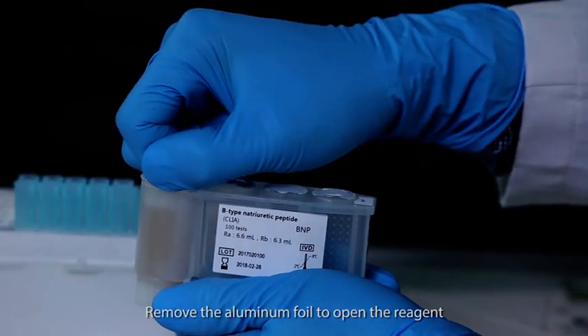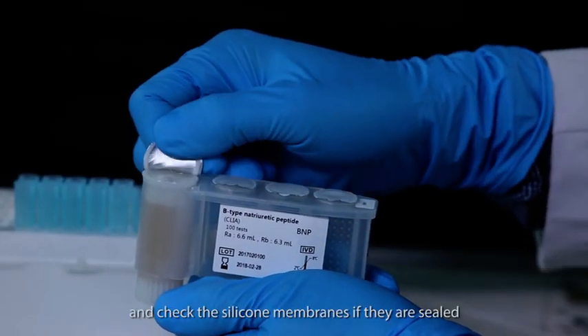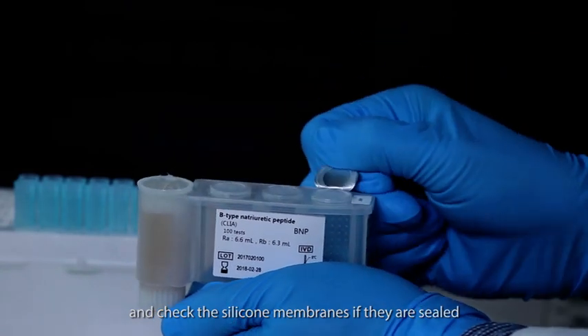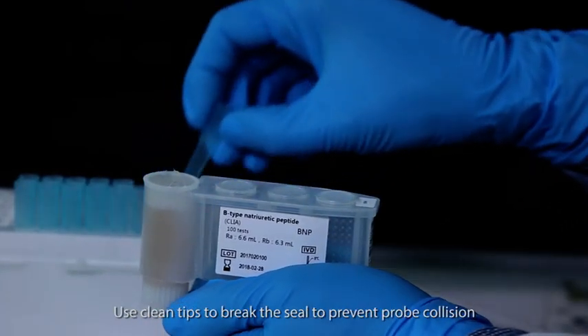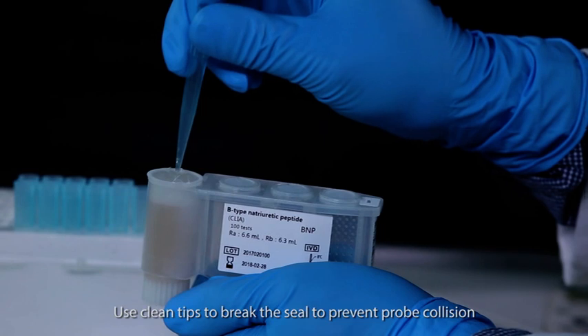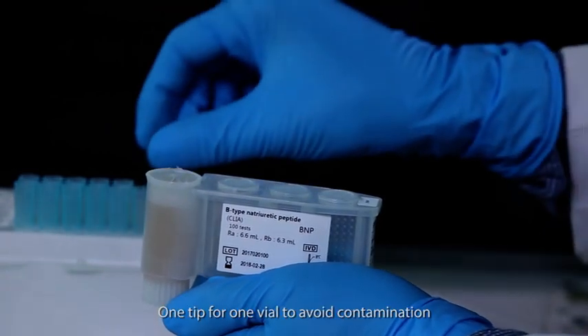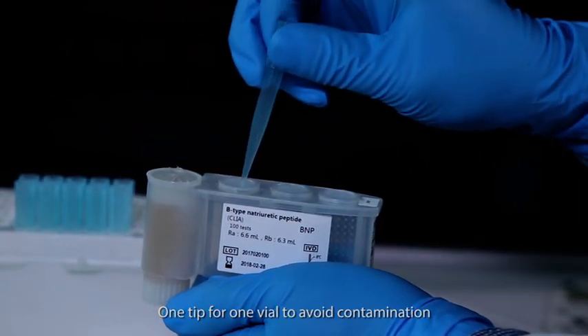Remove the aluminum foil to open the reagent and check the silicone membranes if they are sealed. Use clean tips to break the seal to prevent probe collision. One tip for one vial to avoid contamination.